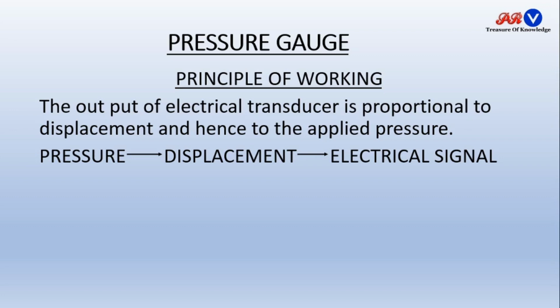The output of electrical transducer is proportional to the displacement and hence to the applied pressure. So we have pressure applied to the Bourdon tube, which produces some displacement. This displacement can be converted into electrical signal for digital measurement of pressure in terms of digital figures. We can use here some pointer and scale arrangement which is calibrated in terms of the pressure, so that indirectly gives us pressure. So this is the principle. Pressure is converted into displacement, and displacement can be measured using electrical signal or some analog techniques.